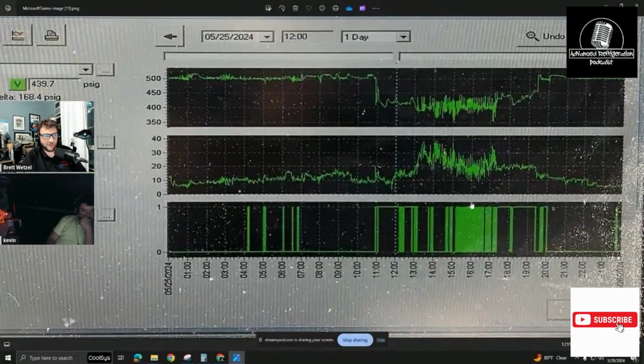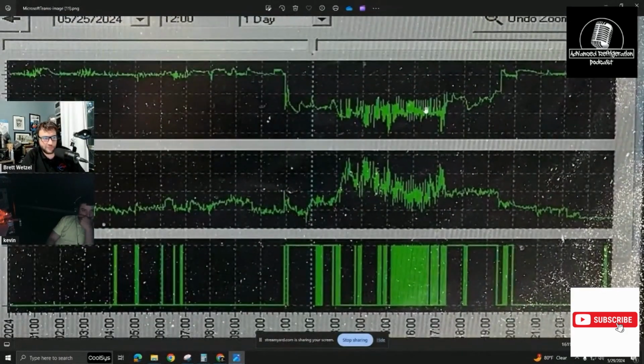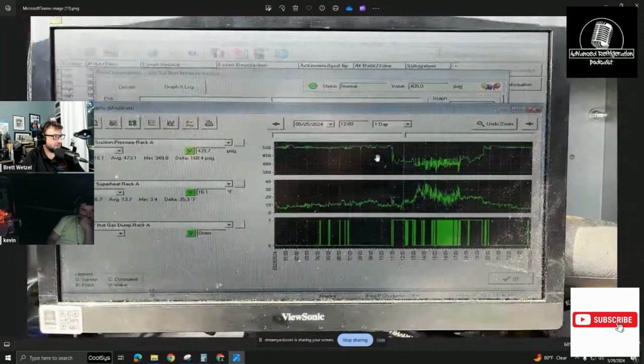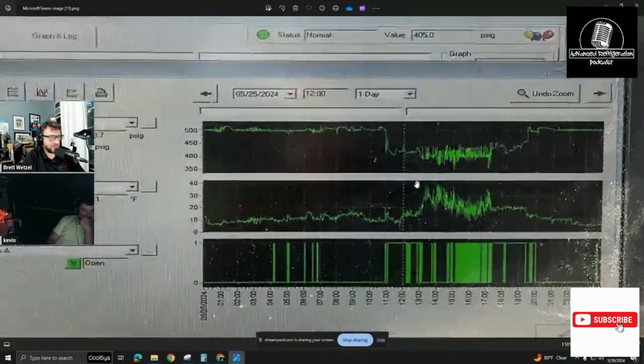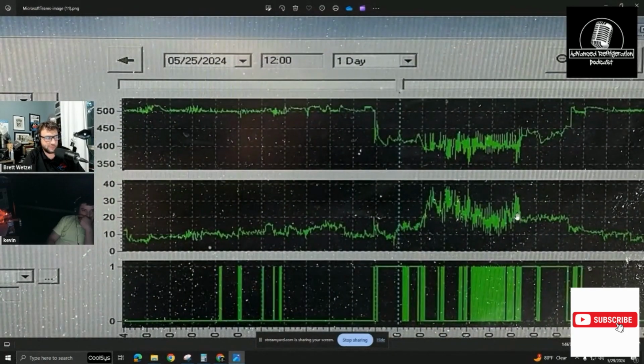But this is where I was saying, where basically he has the, let's see, hold on. Suction pressure and then superheat. All right, suction pressure, superheat, and then when the hot gas is in feeding. So you can see on, off, on, off, on, off. And then once he did that, he also put the liquid injection valve, because I wanted to make sure it wasn't going off on, because I know these racks, they'll inject hot gas and liquid at the same time to keep the suction pressure up in the program.